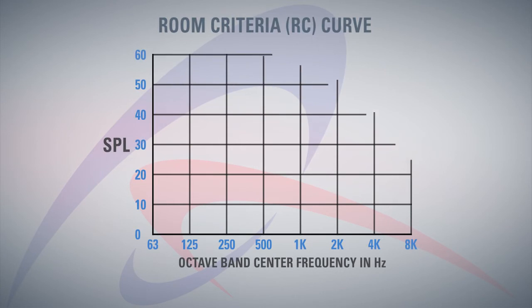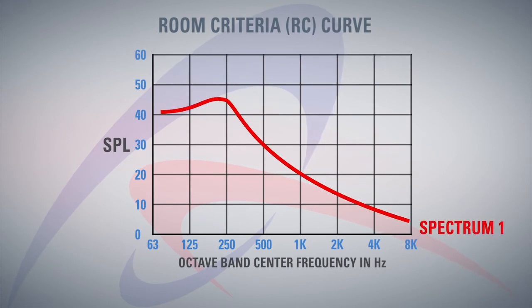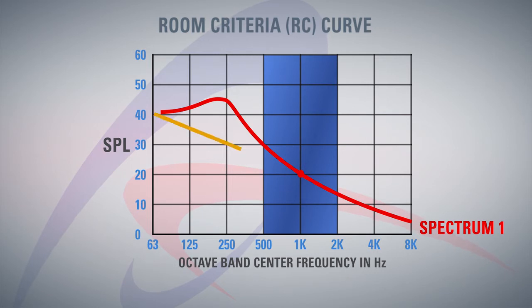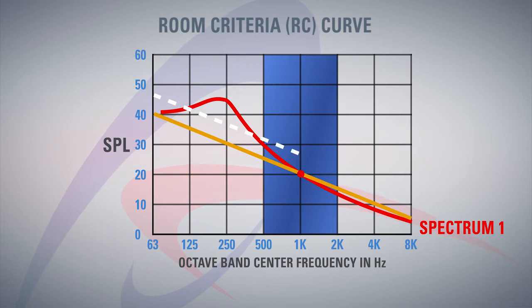The next step was the development of RC curves. An RC curve looks at the same spectrum as an NC curve, but it calculates the average value in the speech interference range — the frequency range that most directly affects your ability to communicate, typically the 500, 1000, and 2000 hertz octave bands. That average becomes your reference point, and from that point you draw a 5 dB per octave slope line. You then look at the actual measurements relative to this line — anything below 500 hertz gets a 5 dB tolerance.